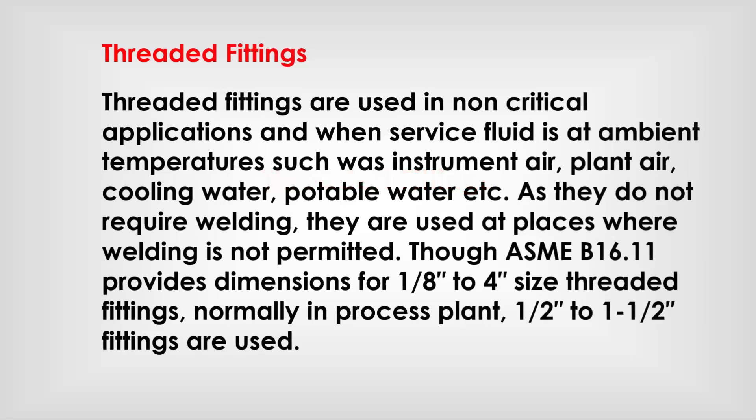Threaded fittings are used in non-critical applications and when service fluid is at ambient temperatures, such as instrument air, plant air, cooling water, potable water, etc. As they do not require welding, they are used at places where welding is not permitted.